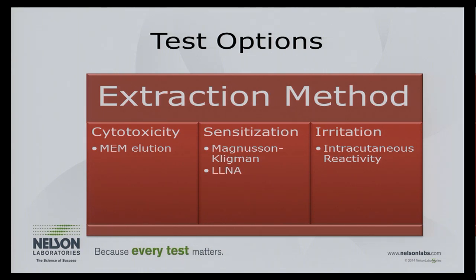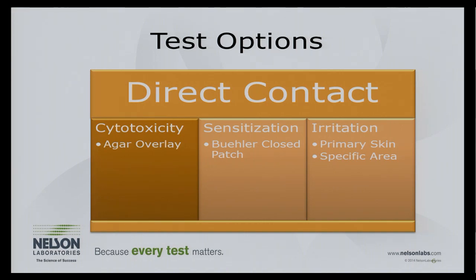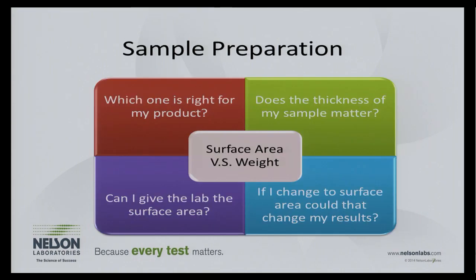The extraction versions of the big three are: MEM elution for cytotoxicity, Magnusson-Kligman or local lymph node assay for sensitization, and intracutaneous reactivity for irritation. The direct contact versions are: agar overlay for cytotoxicity, Buehler method for sensitization, and primary skin irritation. Because most devices contact some kind of fluid in the body, the extraction versions are most common.